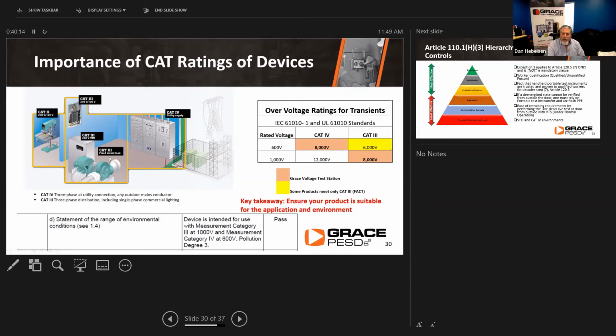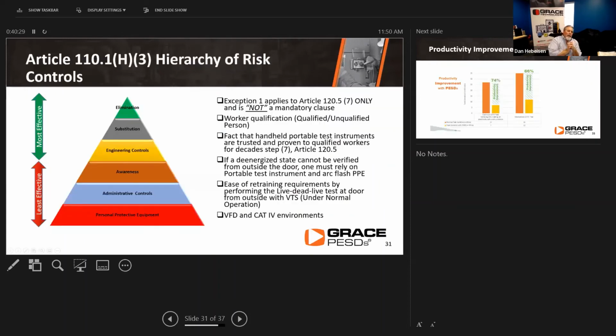The key takeaway here is to ensure that your product is suitable for the application and the environment, and go ahead and quickly install it according to the manufacturer's installation instructions, and then utilize the best practices in Article 110 for reducing risk. So again, we focus on those top three areas of the hierarchy, which are eliminating, substituting, and engineering controls around those hazardous areas. And then we want to make sure that we're keeping people aware of what's going on, administrative controls, and making sure that they are dressing appropriately for the occasions. If we go back to the earlier arc flash presentations that were shown, you saw how big a difference it is when they're properly dressed and protected with the appropriate amount of PPE.